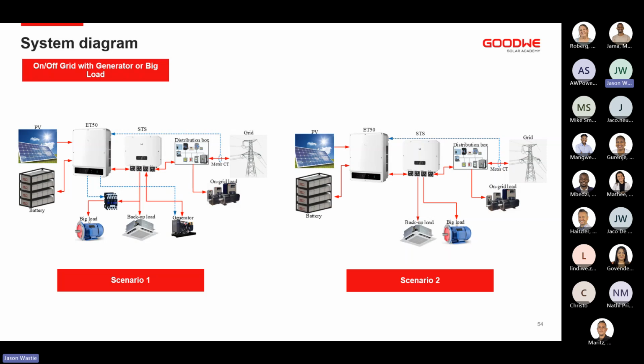And then also still connected with your STS, but with a generator or big load connected. For the first scenario on the left, your big load and diesel generator are connected simultaneously to the STS, and the inverter can control both the start and stop of them through dry node. The diesel generator can also supply backup load or charge the battery. For the second scenario, only the big load is connected to the STS and controlled by the internal switch, which can save the cost of that extra external switch that is connected in the first scenario.